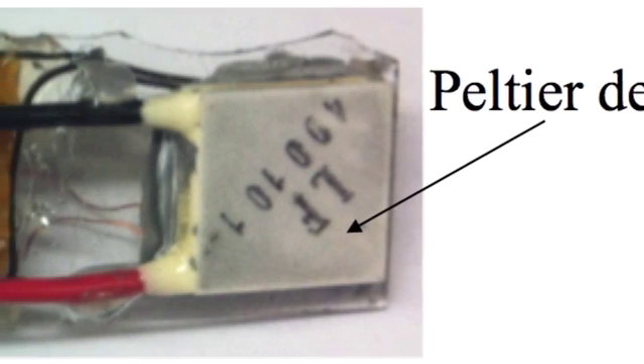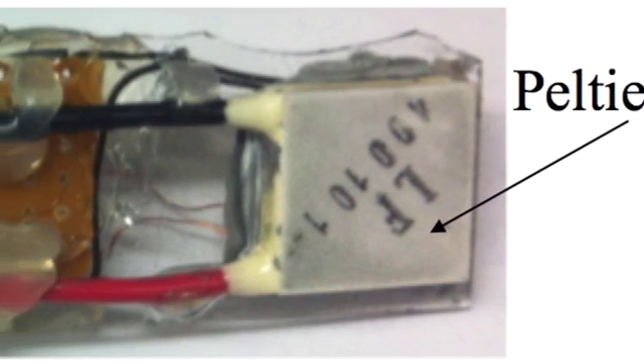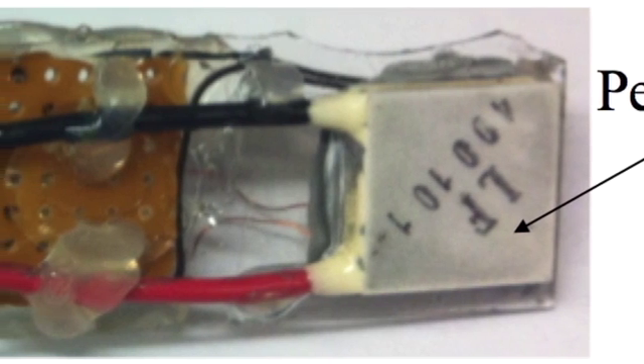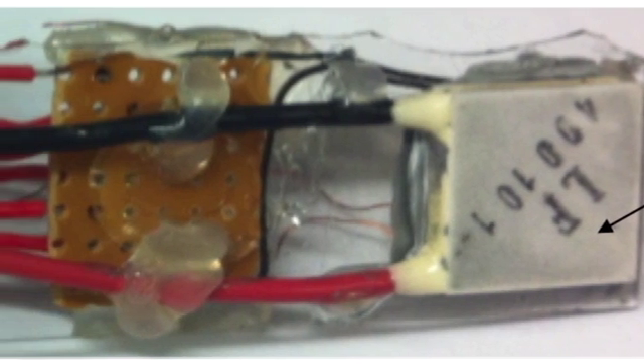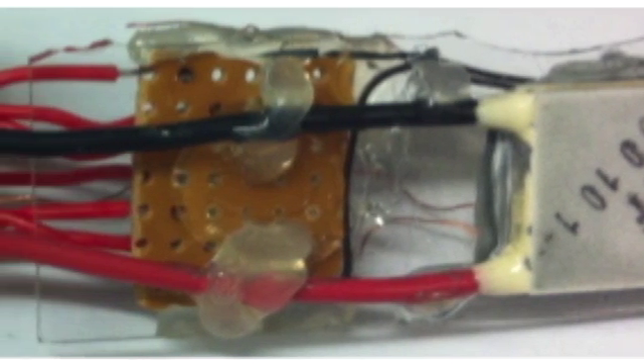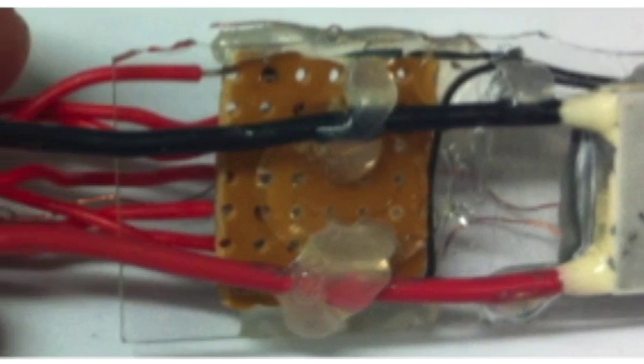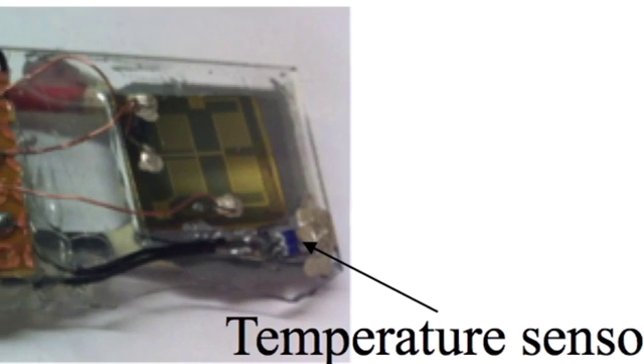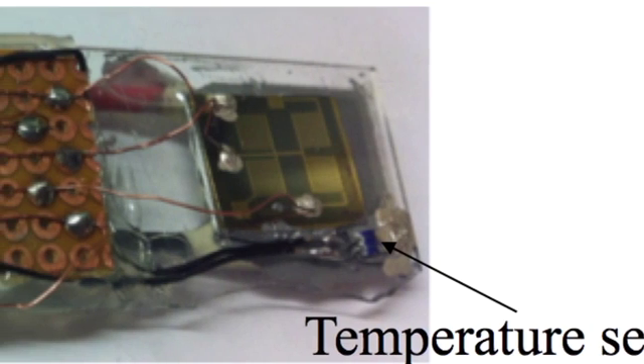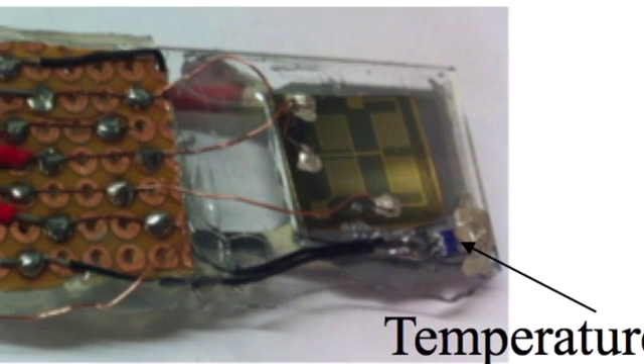On the bottom of our sensor is a Peltier device. With this we're able to heat up the sensor array to 80 degrees during each recovery cycle. We're recording and controlling the temperature during the recovery cycles with the temperature sensor.